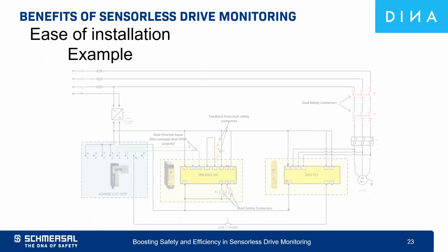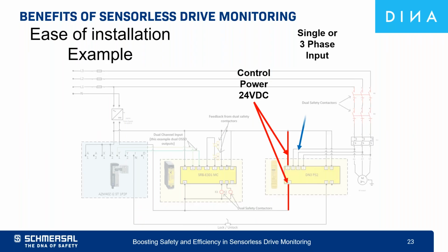Here we see an example of a simple standstill wiring application. We have 24-volt DC for the control power of the standstill monitor. Then we take the single or three-phase information directly from the power wires that go to the motor that's creating the hazardous motion. And then we have an enabling path, which is typically used to unlock a door once the motion has come to a standstill or safe speed.